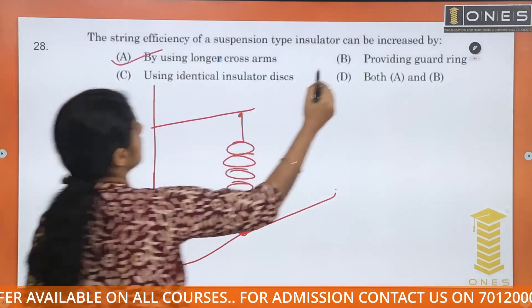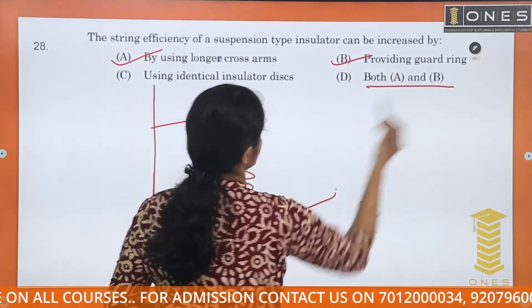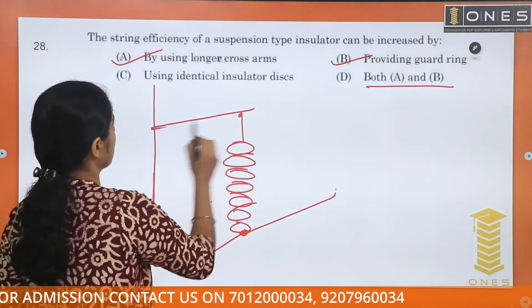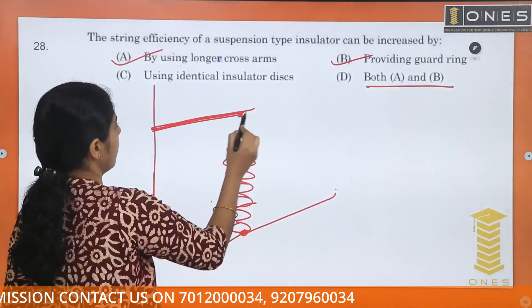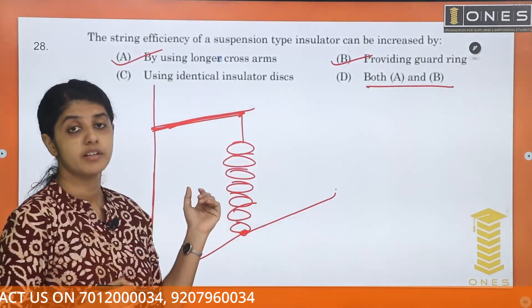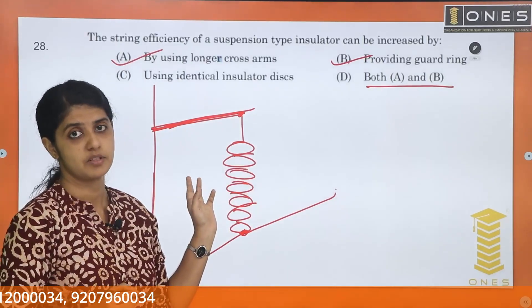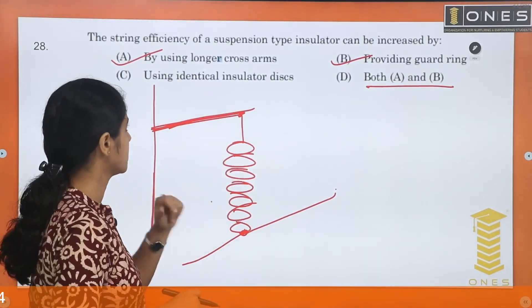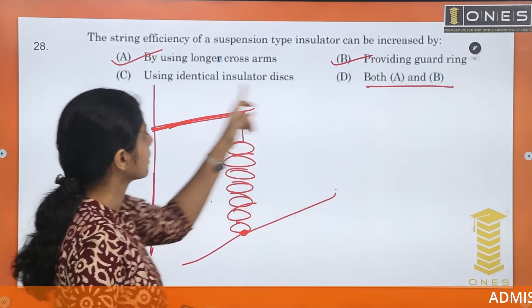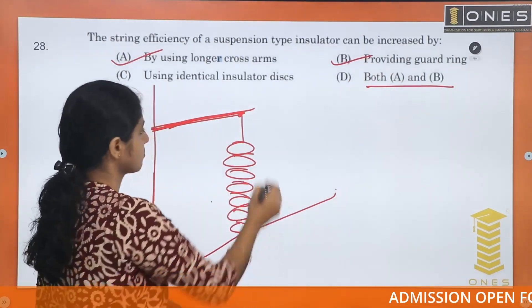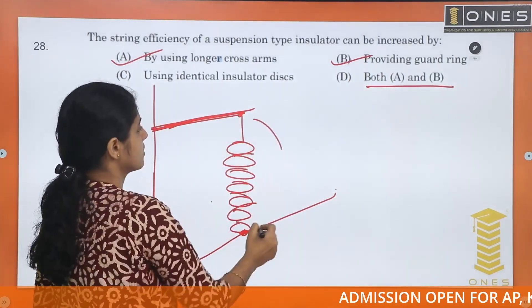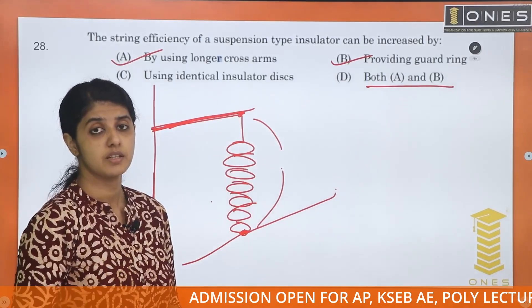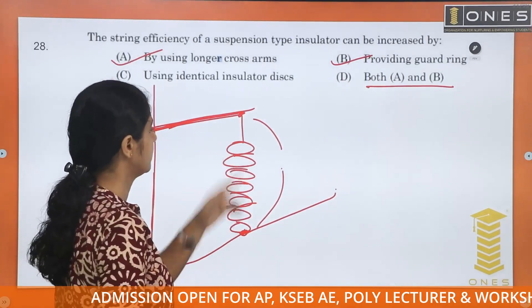The answer is both A and B. Using longer cross arms changes the value of the shunt capacitance, which in turn changes the string efficiency. Providing guard rings also helps to improve the string efficiency.